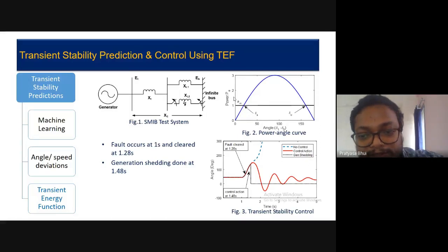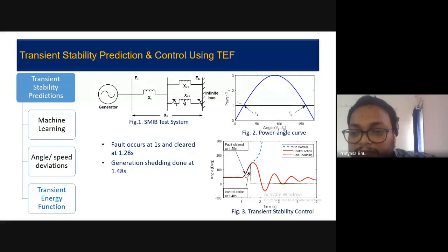So in the energy function approach, suppose there is a fault at 1 second and it is cleared at 1.28 seconds. Then at 1.28 seconds, after fault clearing, we will predict whether the system will remain stable or not. If it is unstable, it will send some control signal to the generating plants. It can be generator shedding, it can be fast valving or something else, or it can be turning on some braking resistors. So the control signal can be sent to the generating plant. Without control action, it becomes unstable. With control action, you can see that it becomes stable.